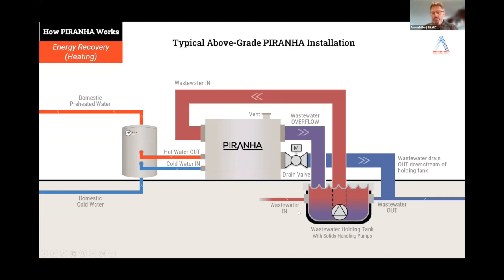So we can do what's called multi-pass. We've got 70 some odd degree water here, and we're outputting up to 140 degree water. So sometimes you have to run that water through multiple times to get enough energy out of it to make that hot water for your plant.